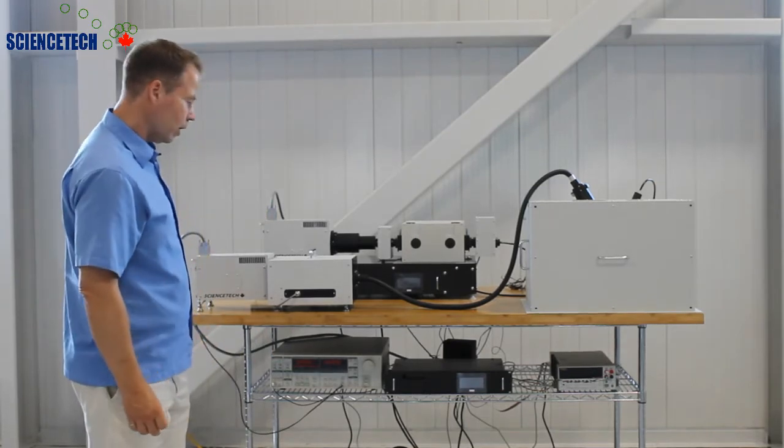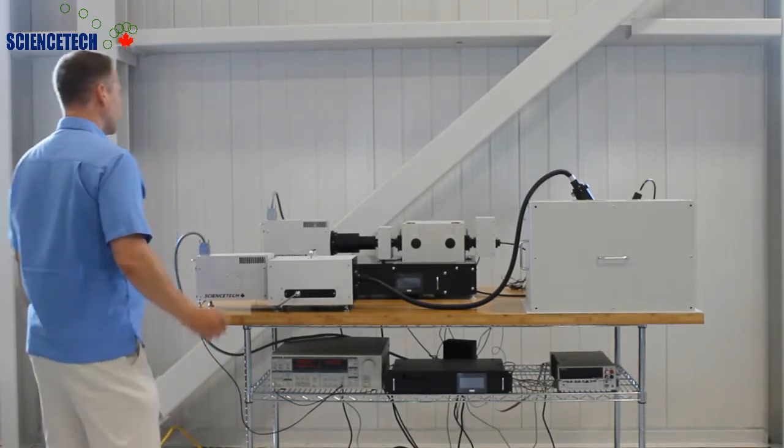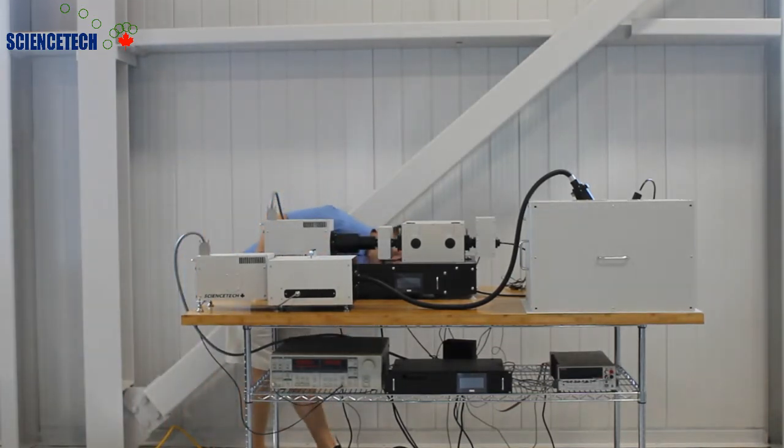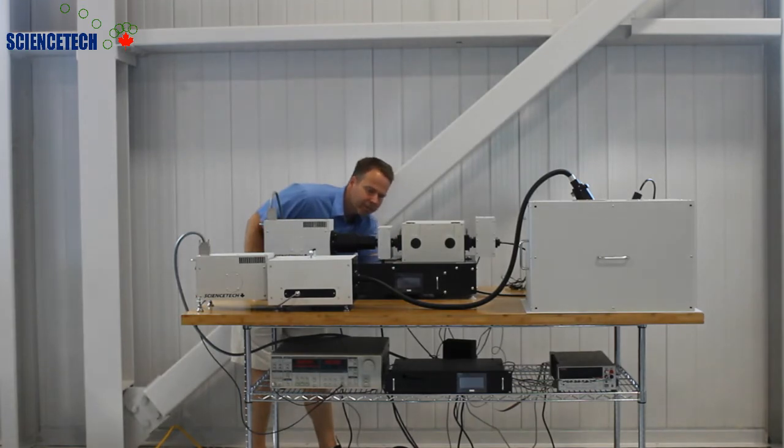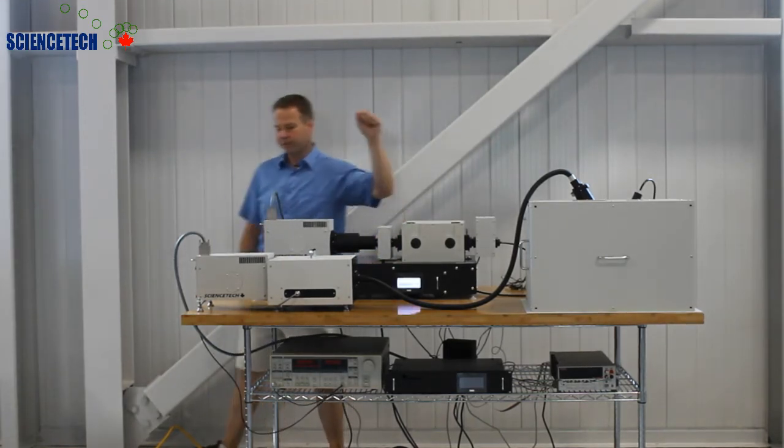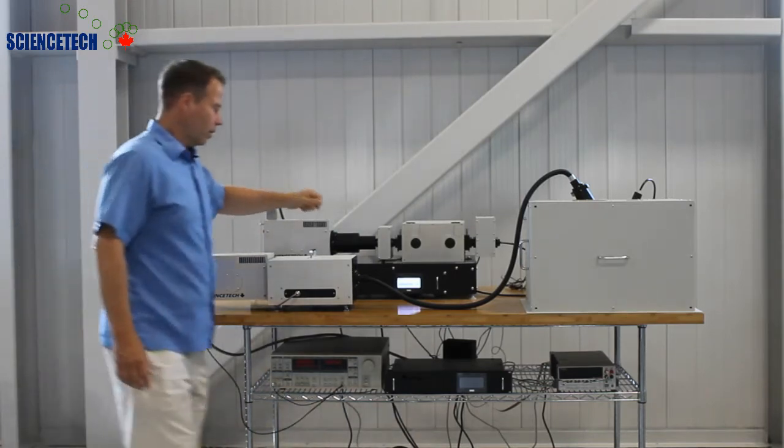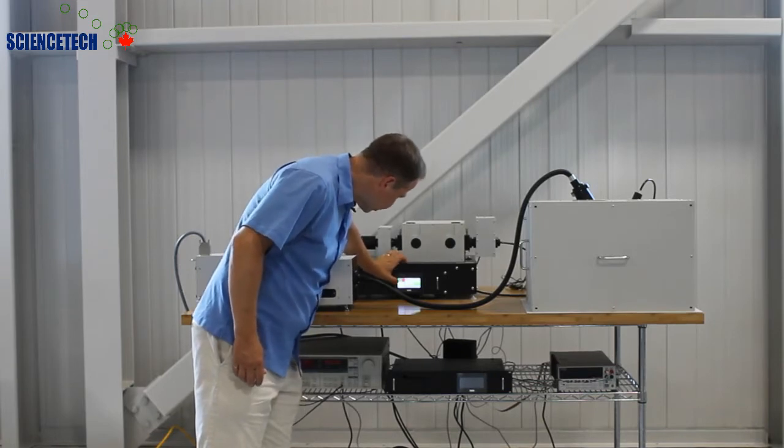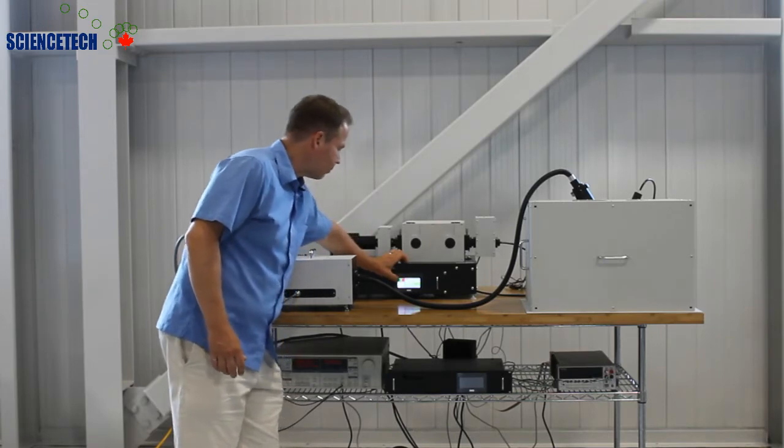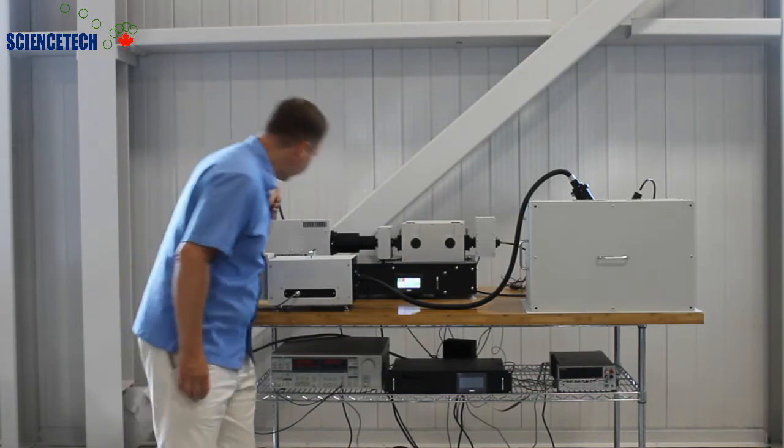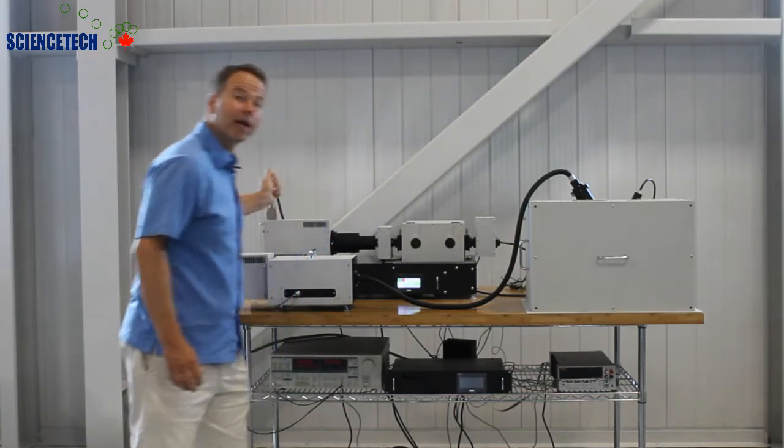Let's turn it on. There's a lot of components here. We'll start by turning on the TLS. There's a switch on the back here which turns on the touchscreen power supply. I go through the menu to turn on the fans for the lamp and to ignite the lamp itself. And now the lamp is on.